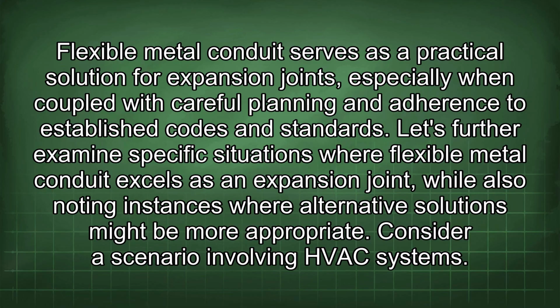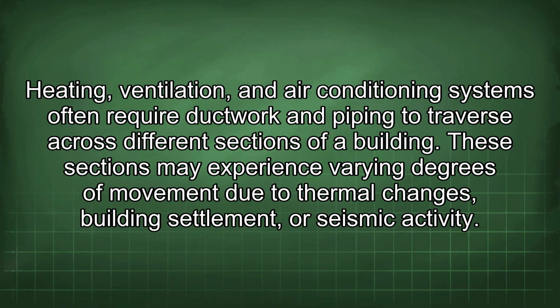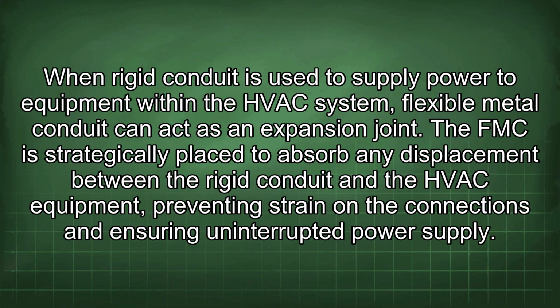Consider a scenario involving HVAC systems. Heating, ventilation, and air conditioning systems often require ductwork and piping to traverse across different sections of a building. These sections may experience varying degrees of movement due to thermal changes, building settlement, or seismic activity. When rigid conduit is used to supply power to equipment within the HVAC system, flexible metal conduit can act as an expansion joint. The FMC is strategically placed to absorb any displacement between the rigid conduit and the HVAC equipment, preventing strain on the connections and ensuring uninterrupted power supply.